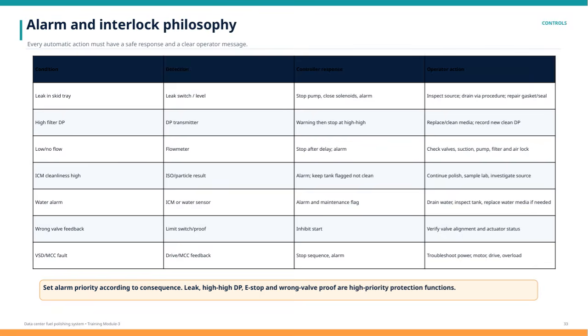When cleanliness levels in the ICM are too high, indicated by ISO or particle results, an alarm sounds and the tank is flagged as not clean. The operator should continue polishing, send samples to the lab, and investigate the contamination source. Water alarms from the ICM or water sensors also trigger alarms and maintenance flags, signaling operators to drain water, inspect the tank, and replace water media if necessary.